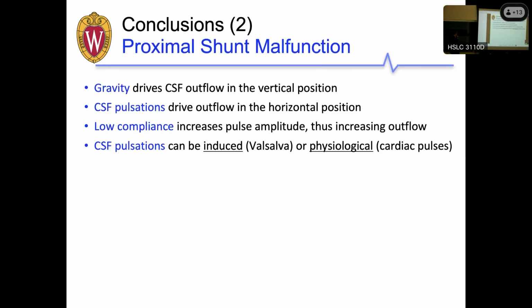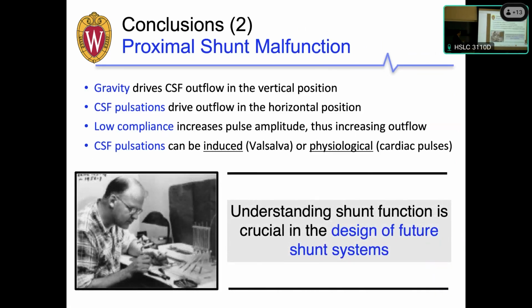We find that gravity and CSF pulsations cause overdrainage in shunt systems, evident clinically and on the bench, and that this can happen in the horizontal or the vertical position. It can be due to general physiologic issues such as Valsalva maneuvers and physiological pulses, which tells us that the only way we're going to improve on current shunt systems... you can imagine how many iterations of programmable and sophisticated valves have been introduced in the past 6 decades, but nothing has improved the shunt obstruction rate. That's because they're all based on gravitational forces.